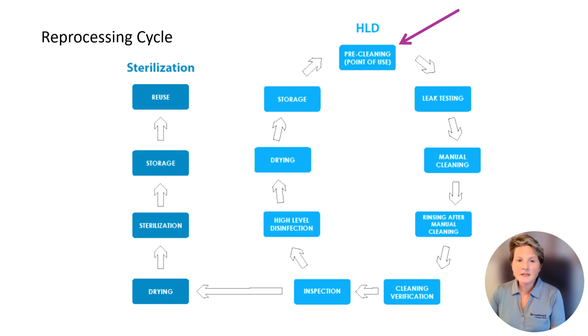you start up at the top for the HLD part where it says pre-cleaning or the point of use cleaning. Then of course you move into leak testing, then manual cleaning, then rinsing after the manual cleaning, cleaning verification and inspection, and then high-level disinfection, drying, storage. And of course, to the left there, you see what the process would look like if you were going to be sterilizing instead of high-level disinfecting.